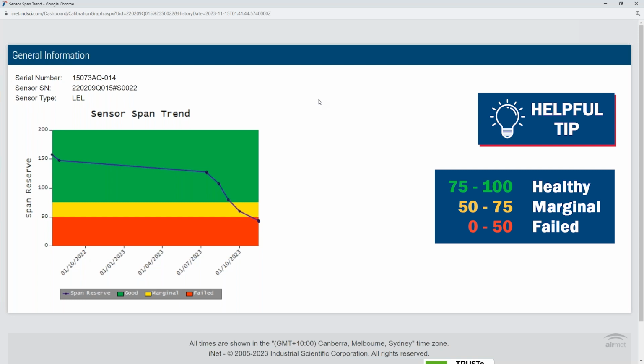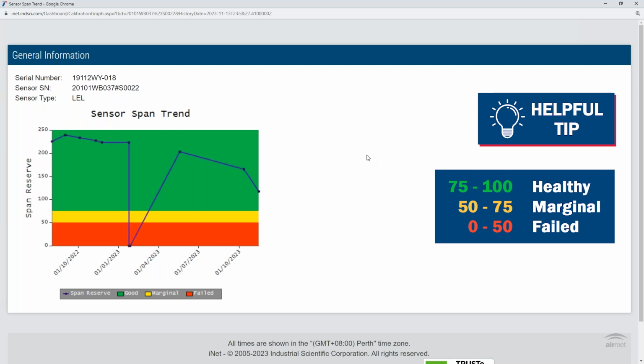This is an example of another LEL sensor. However, this particular graph shows the typical trend of sensor decline. The span reserve results can also be used as a diagnostic tool. Instruments may also fail calibration due to issues with the docking station, such as restricted tubing or improper mounting. As shown here, due to improper mounting of the instrument, the docking station recorded a failed calibration test. Subsequent tests show the sensor functioning as normal. Sudden unexpected fails after a successful calibration may indicate the instrument was not docked properly. It is important to force a calibration after a failed or marginal result to diagnose the issue.